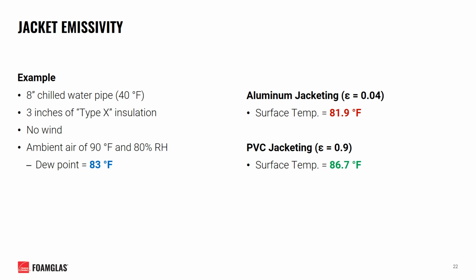When covering our insulation with brand new aluminum jacketing, the surface temperature we get is 81.9 degrees. This is less than the dew point of the surrounding air and becomes an immediate concern for surface condensation on the jacketing to take place. However, when we take the same system and cover it with our PVC jacketing, more heat from the environment is allowed to transfer into the jacket surface, giving us a surface temperature of 86.7 degrees F, safely above the dew point where surface condensation will become an issue.